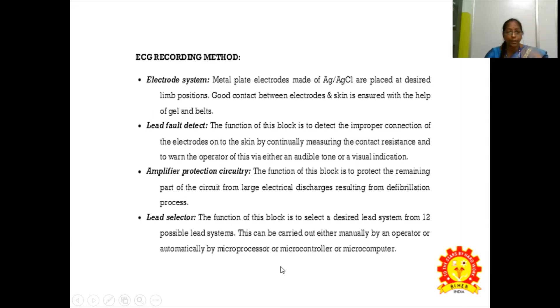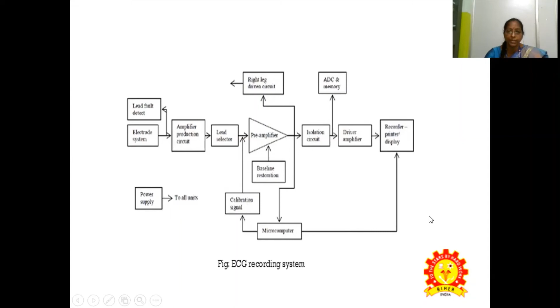We have amplifier protection circuits, a lead selector, a pre-amplifier, baseline restoration, an isolation circuit, and a driver amplifier to drive the recorders or the output monitors of the display units, which have to be driven by supplying the required voltages. And we have an analog to digital and memory section, and the microcomputer gives all the instructions to all the sub units. You have to calibrate the signal according to the system, so the electrical output is calibrated for the desired diagnostic measurements.